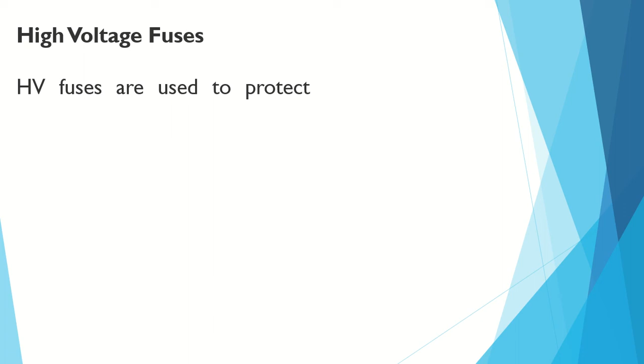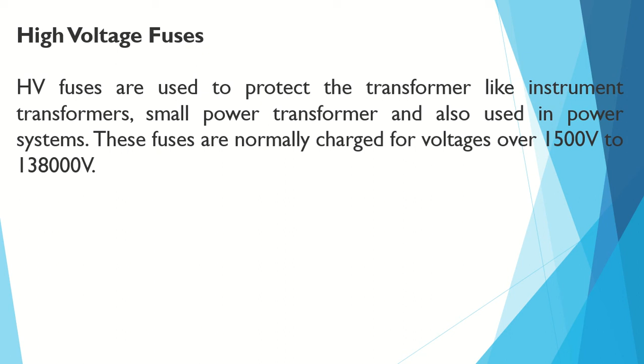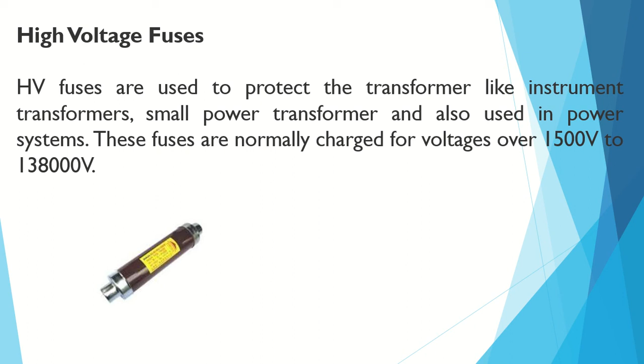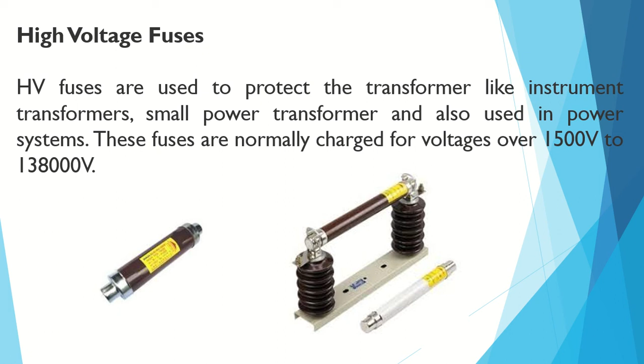High voltage fuses are used to protect transformers, like instrument transformers, small power transformers, and are also used in power systems. These fuses are normally rated for voltages over 1500 volts up to 138,000 volts. This is a high voltage fuse - it's a big one like this. We can find it on poles or structures, transformer structures, and substations. There are two colors: one is sand color and the other is white.